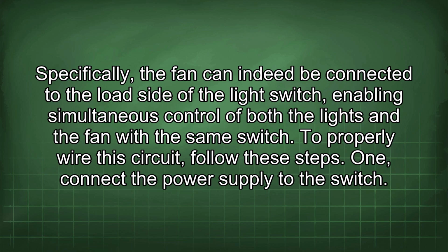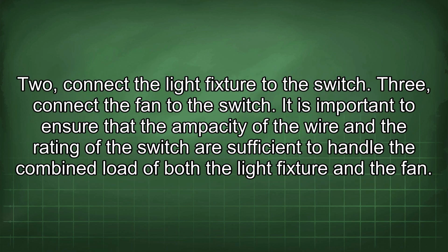1. Connect the power supply to the switch. 2. Connect the light fixture to the switch. 3. Connect the fan to the switch. It is important to ensure that the ampacity of the wire and the rating of the switch are sufficient to handle the combined load of both the light fixture and the fan.